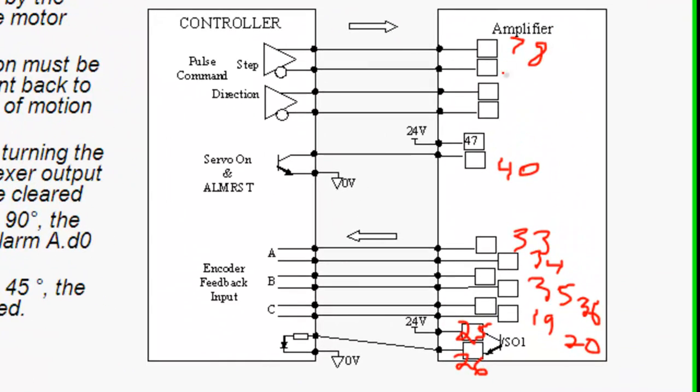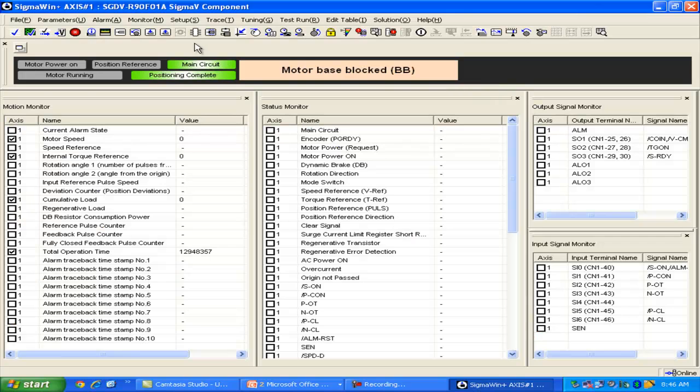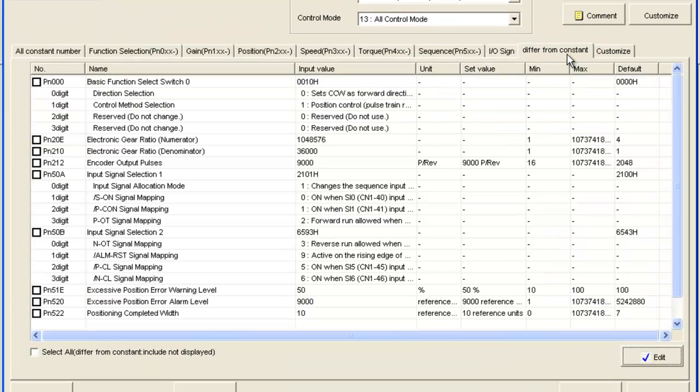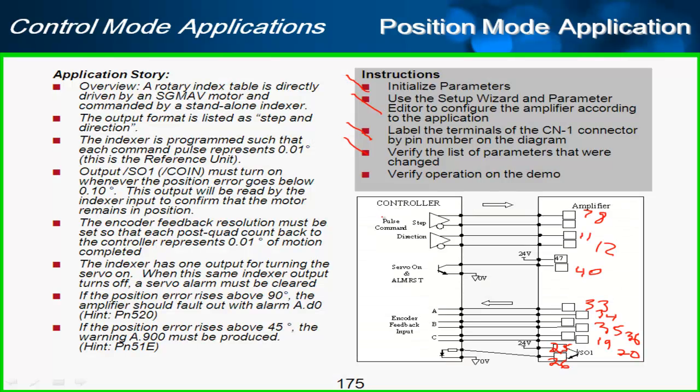I'm missing the command reference here, step and direction. And that's up here to the reference here, pulse and sign, 7 and 8 and 11 and 12. So where am I at? I've initialized the parameters, I used the setup wizard and the parameter editor, labeled my terminals. I could see a list of the parameters that have been changed by going to the parameters menu again. Opening up differ from constant and just take a look here, be sure that everything is in place. And now let's verify operation on the demo.